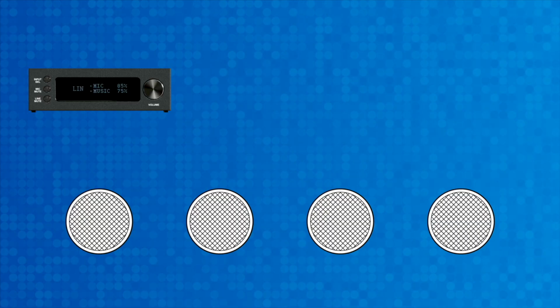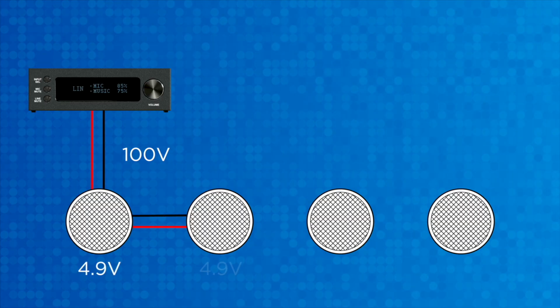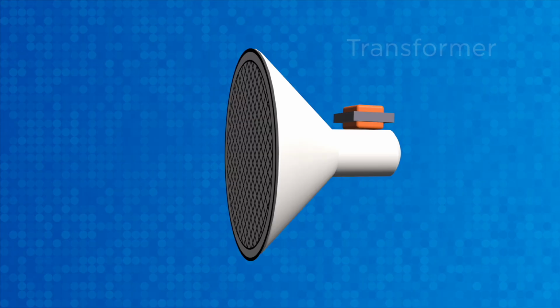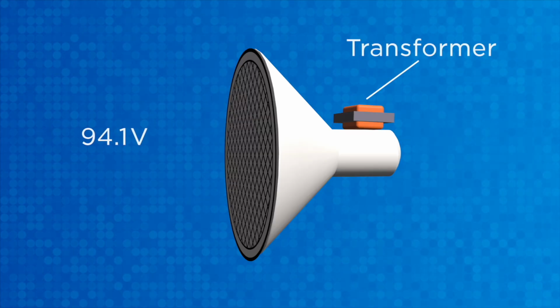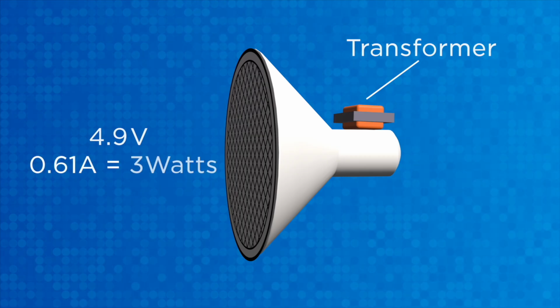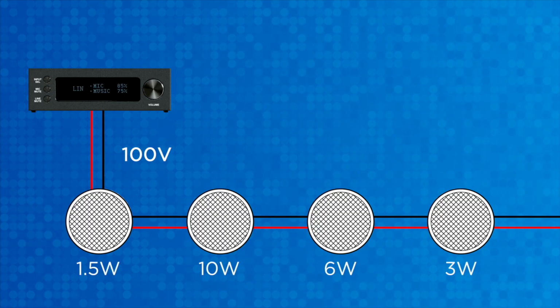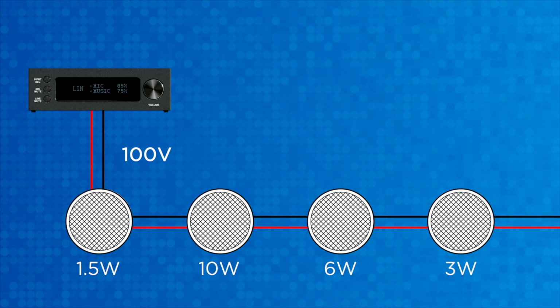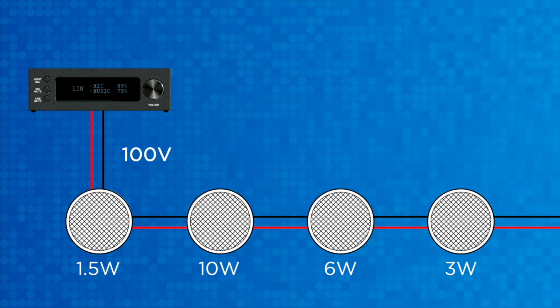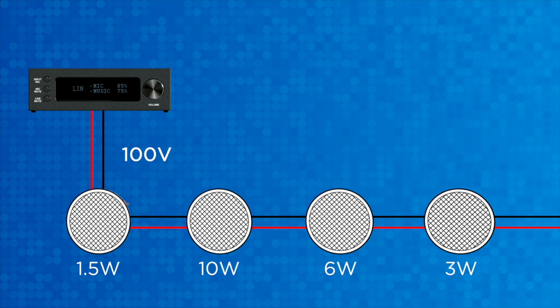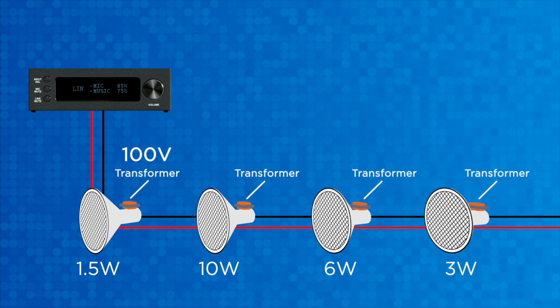The amplifier outputs the audio signal at 100 volts and feeds to the speakers through a twin cable. Each speaker has its own transformer attached to it that reduces that 100 volts peak signal back down to a lower regular voltage that the speaker can handle. Now, the transformer also may have many different tap points taken off the transformer that will let you choose how much power and volume each speaker will receive, so you can tailor it nicely. The speakers are connected in parallel, which means that they share the same cable and signal, and it's wired in a daisy chain type topology. But they do not affect each other's impedance or load, as each individual speaker has its own transformer mounted to it. So let's talk about measurements.